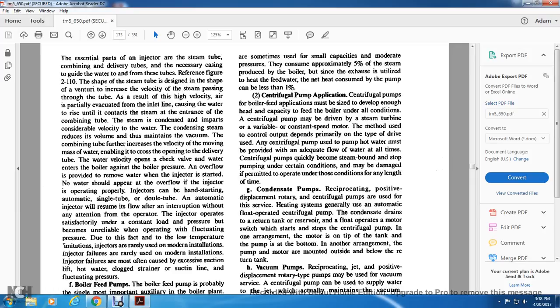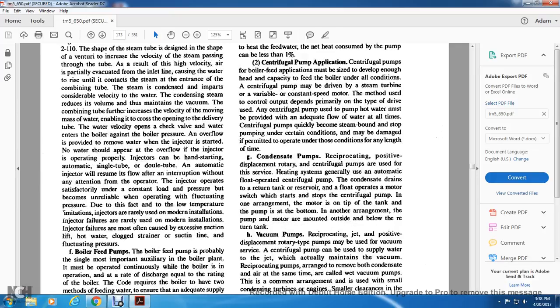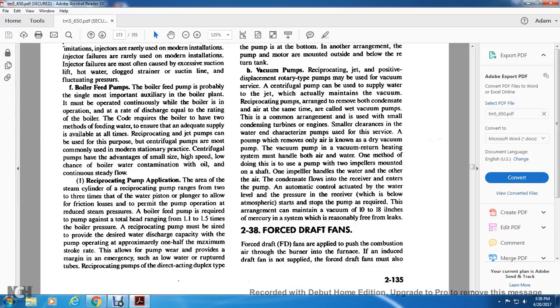Injector failures are most often caused by excessive suction lift, hot water, a clogged strainer on the suction line, and fluctuating pressures. Boiler feed pump. The boiler feed pump is probably the single most important auxiliary in the boiler plant. It must be operated continuously while the boiler is in operation. The rate of discharge is equal to the rating of the boiler.